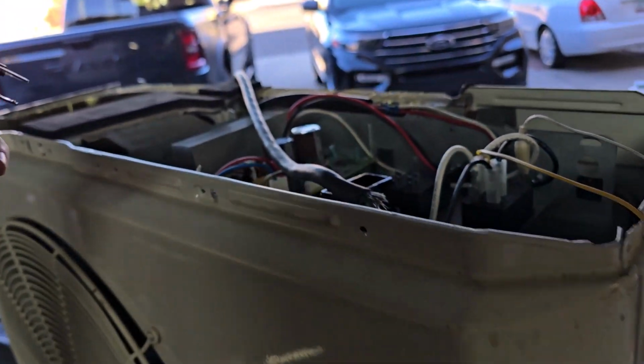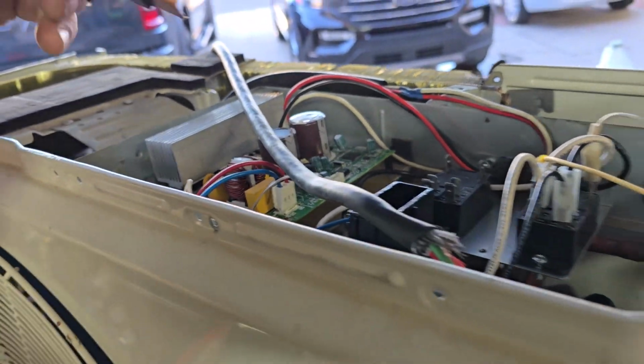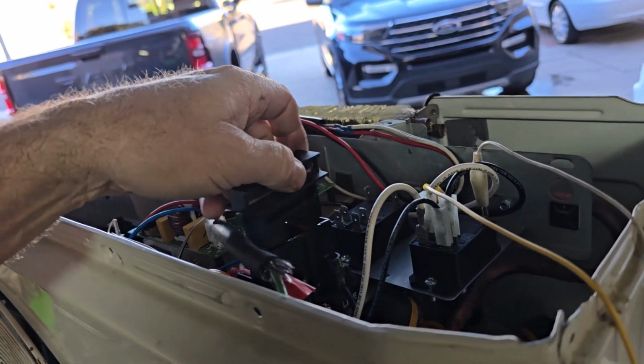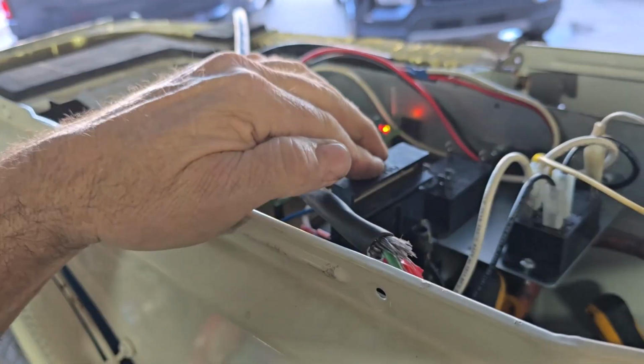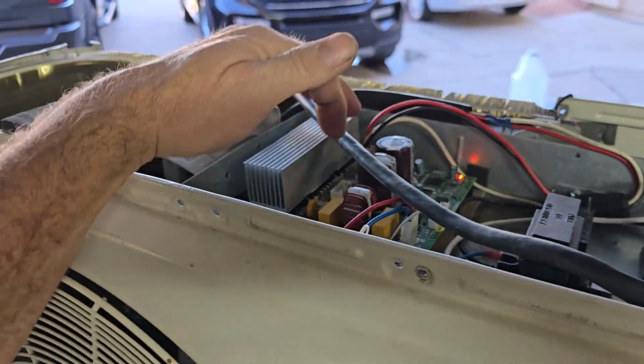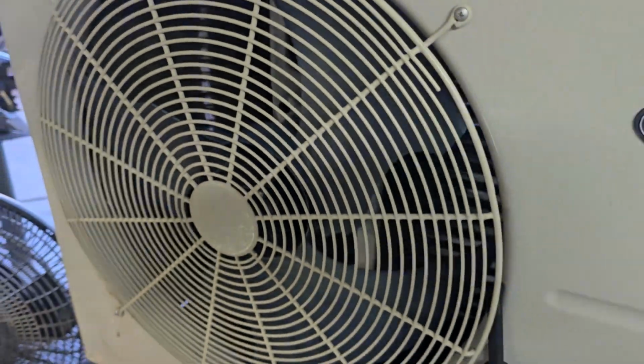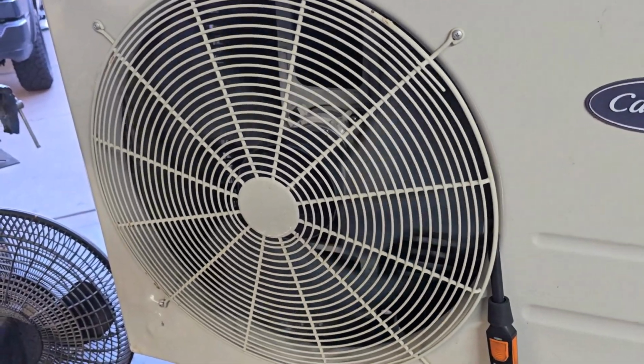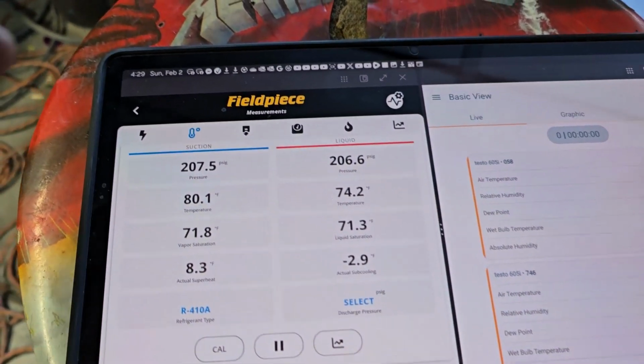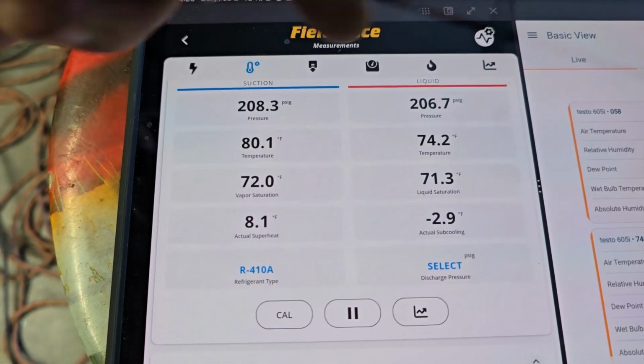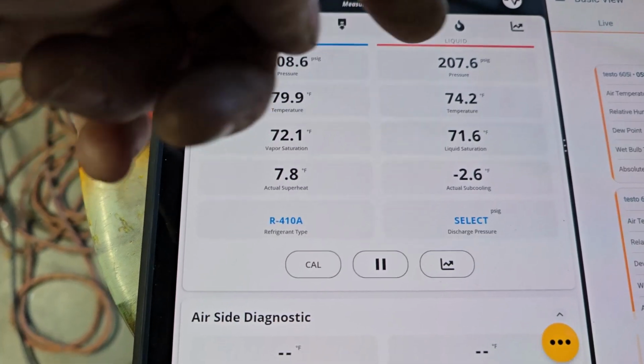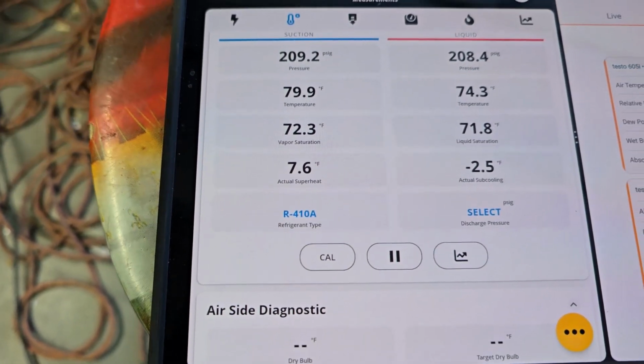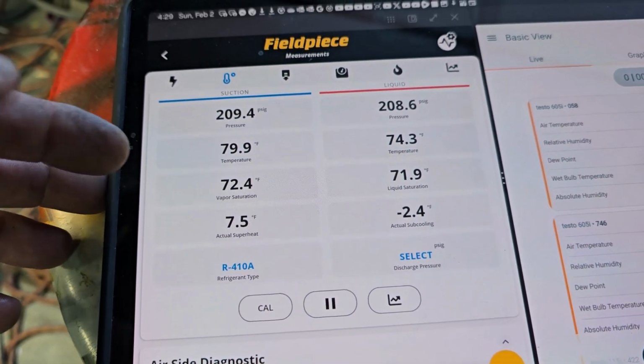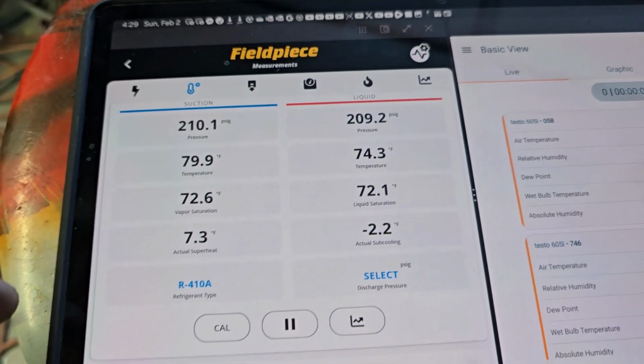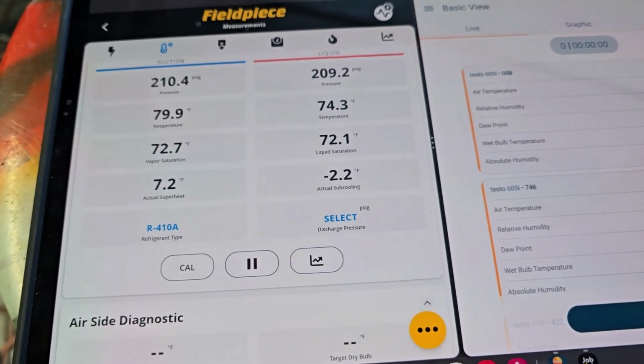Okay, front panel in place. We've still got the fan wired direct, so as soon as I put power, it should start where the potentiometer is left. That pop was normal, so the capacitors are drained completely out. So the fan motor should start. Looking over here, FieldPiece pressures are equalized, about 80 degrees. It is warm today. So when it runs, we'll look at that.